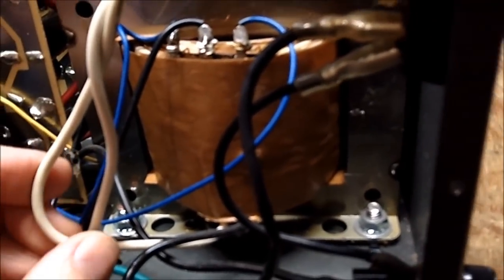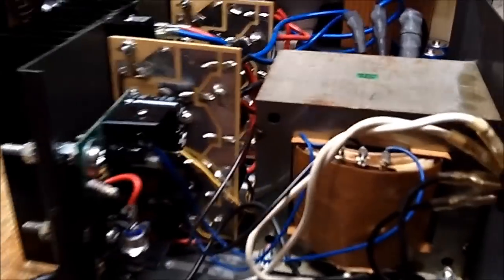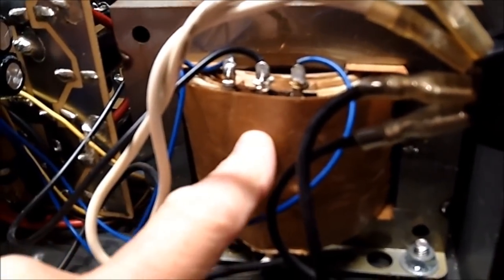Before we do anything, we're going to check the primary - I've got to turn this around. Alright, and this is your primary side of the transformer, and this is what we're worried about. Here's your input right here. Now, there is a tap that goes off and goes over here. So I'm going to have to get the schematic of this if this transformer is good.